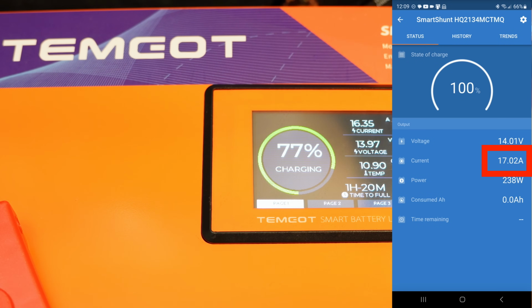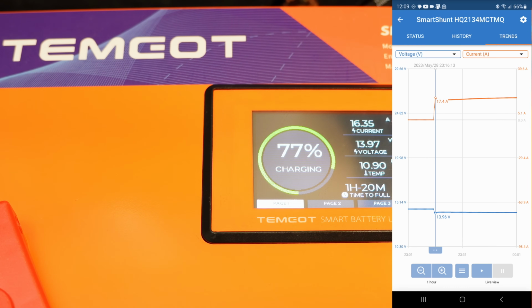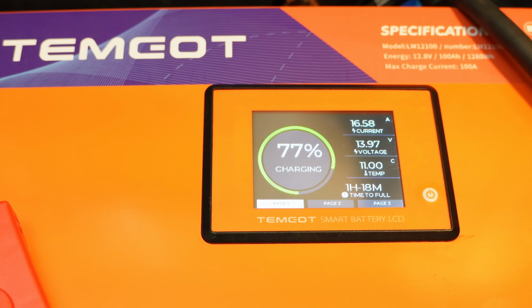Let's see if we can find out when this actually started charging, because it's about 3 hours from when we last checked in. Looking at the trends, we went from that top line with no current going in to where we hit 17 amps. That seems to have tripped right around 2 hours and 15 minutes after this thing was frozen solid. That's how long it took to thaw out and automatically begin charging. So I'd say low temp cutoff definitely works.